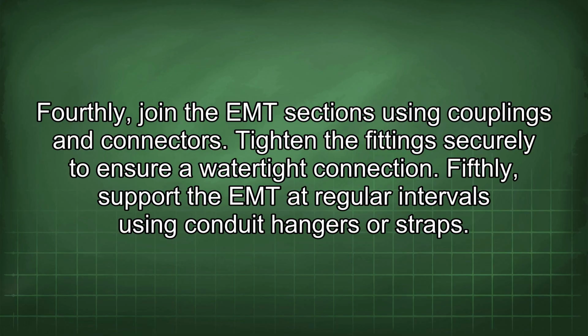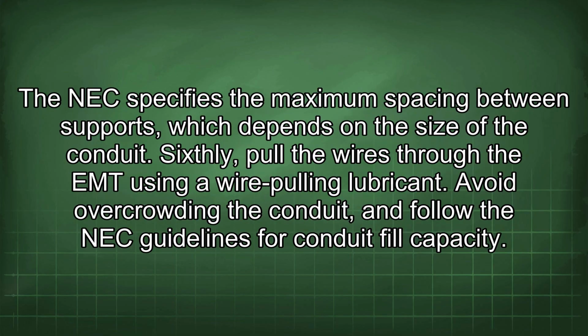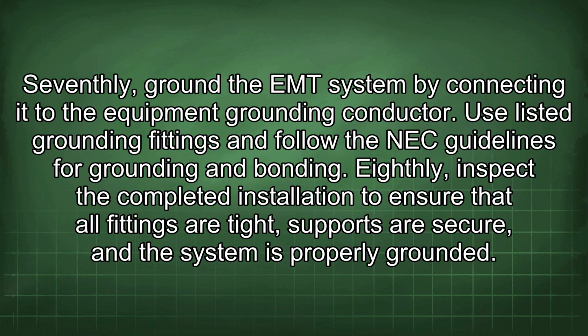Fifthly, support the EMT at regular intervals using conduit hangers or straps. The NEC specifies the maximum spacing between supports, which depends on the size of the conduit. Sixthly, pull the wires through the EMT using a wire pulling lubricant. Avoid overcrowding the conduit and follow the NEC guidelines for conduit fill capacity. Seventhly, ground the EMT system by connecting it to the equipment grounding conductor. Use listed grounding fittings and follow the NEC guidelines for grounding and bonding.